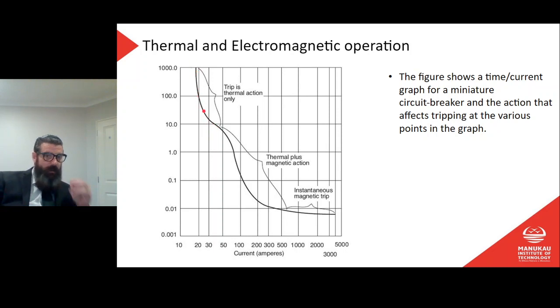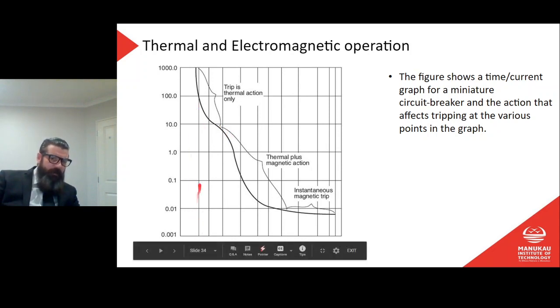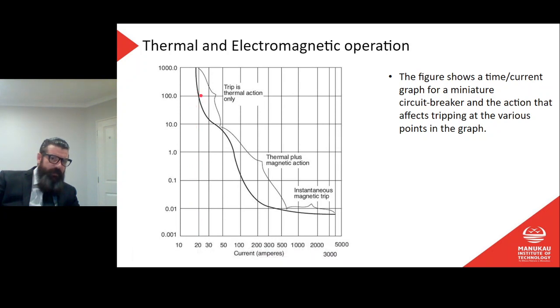So that's the heating time, the time it takes for that bimetal to heat and start to open. Once we start to get it up towards 50 amps, by the way, if that line is 20 amps there, and we're talking about 100-second tripping time, this must be maybe a 16 amp breaker or something like that. Anyway, once we start getting up towards around 50 amps, then we've got thermal and magnetic. So this line continuing there would be thermal only.